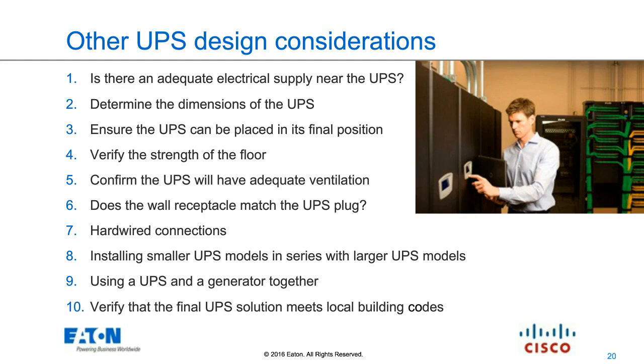Ventilation. UPSs today are running upwards of 93+% efficiency, but on a large enough system, that 7% of inefficiency becomes heating for the room. And you need to get that warm air out of the rack. So the rack can't be pressed up against the wall. The UPS probably can't be pressed up against the back wall. And there must be sufficient cooling into that space to account for it, because ultimately all white space hardware is 100% inefficient. Whatever goes into the data center becomes heat. So that must be taken into consideration for ventilation and cooling.